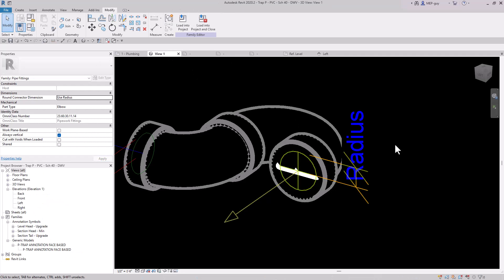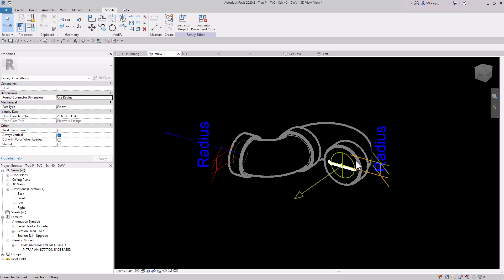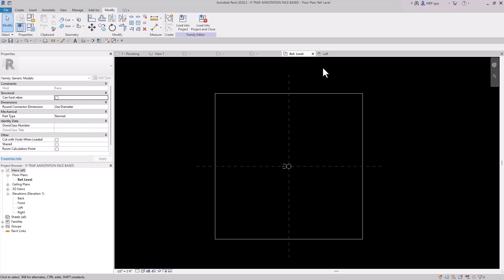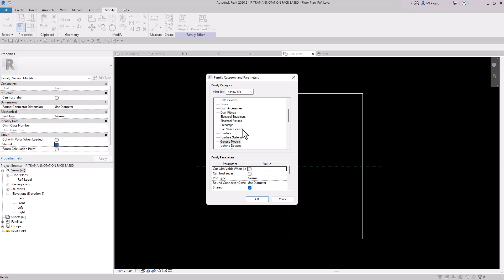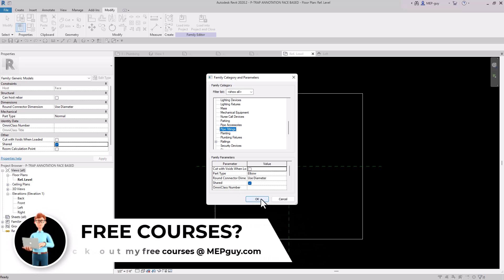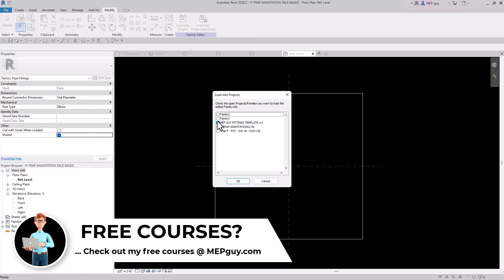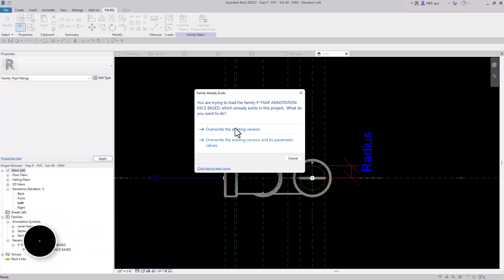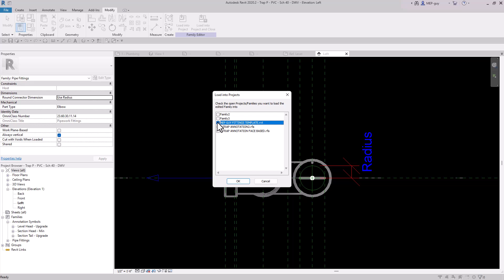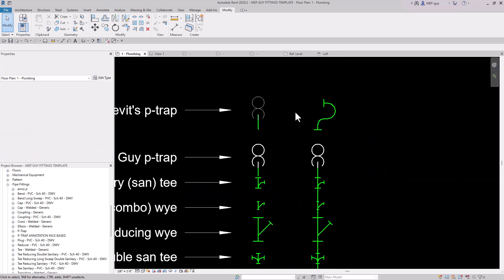Let's go back to our P-trap family and then back to the face-based family. We need to use the shared parameter — this will apply the same properties from this family to our P-trap family. We also need to change the family category to Pipe Fittings and make sure it's set as an elbow. Confirm it's shared, click OK, then load it back into the P-trap family — Trap P — overwrite the existing version, and load this into our main project. Overwrite, and as you can see, the P-trap now shows perfectly.